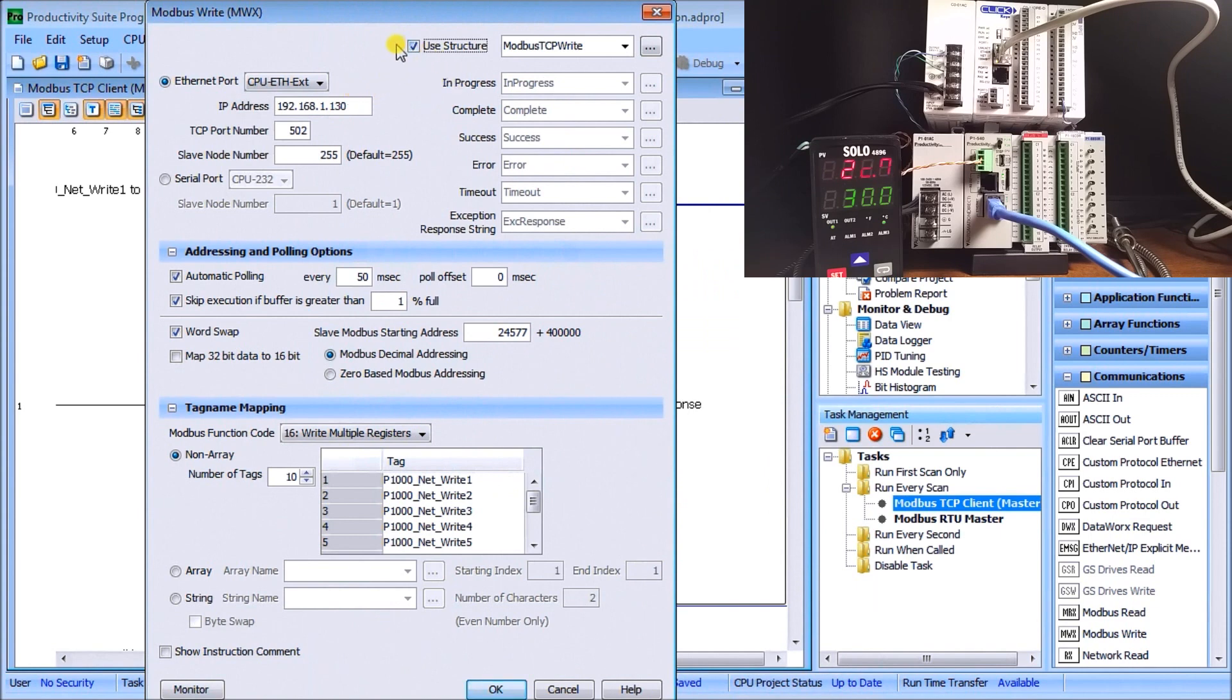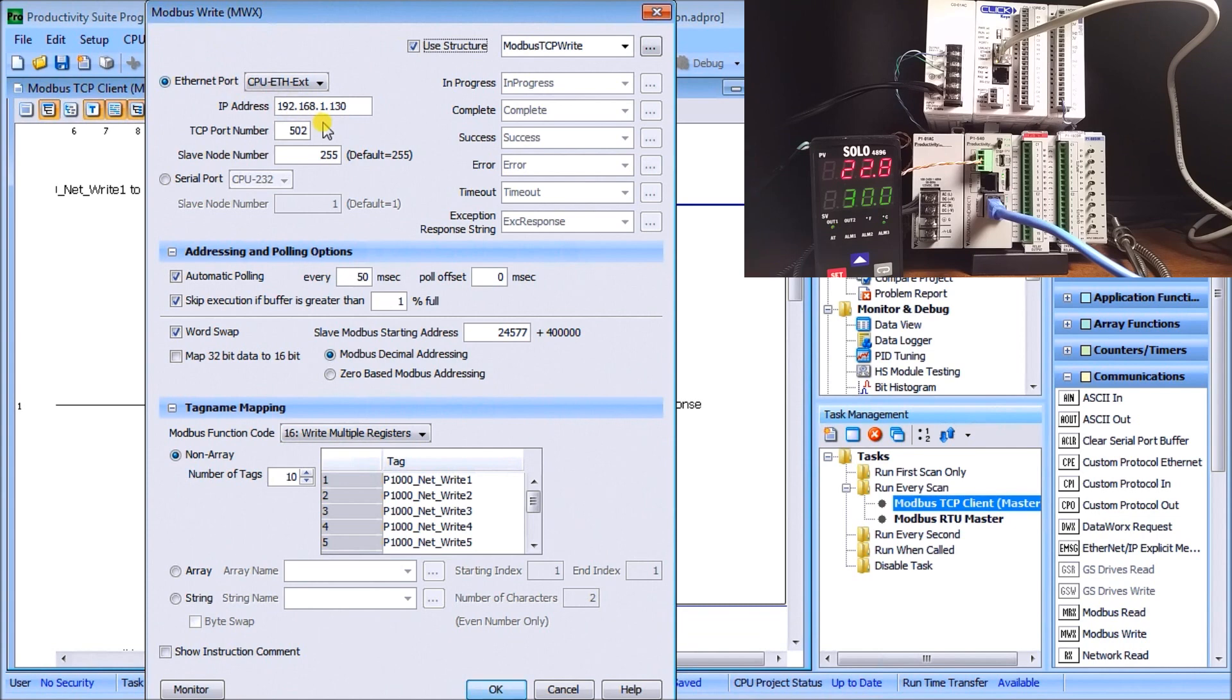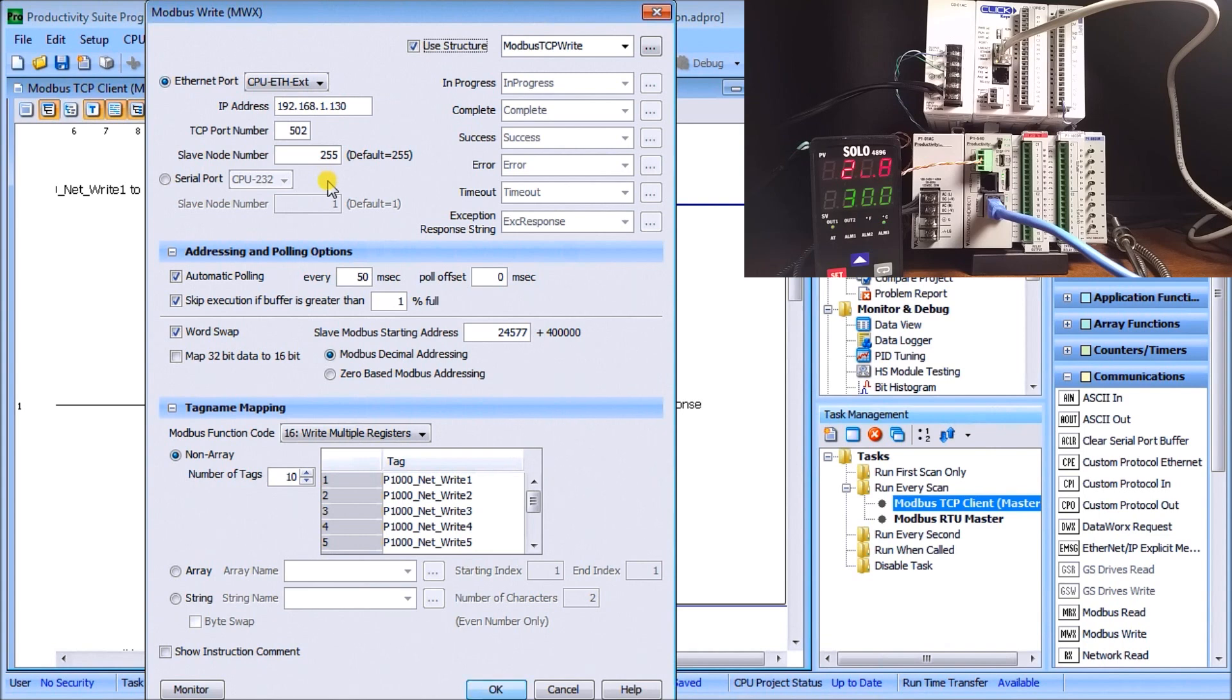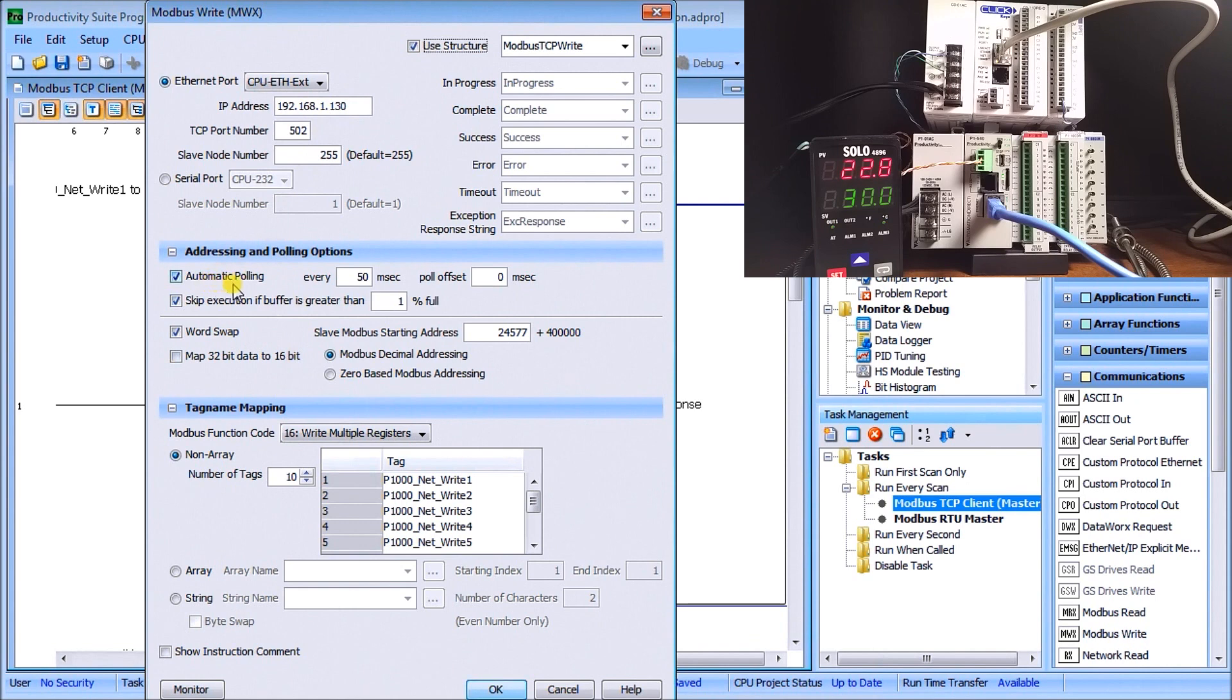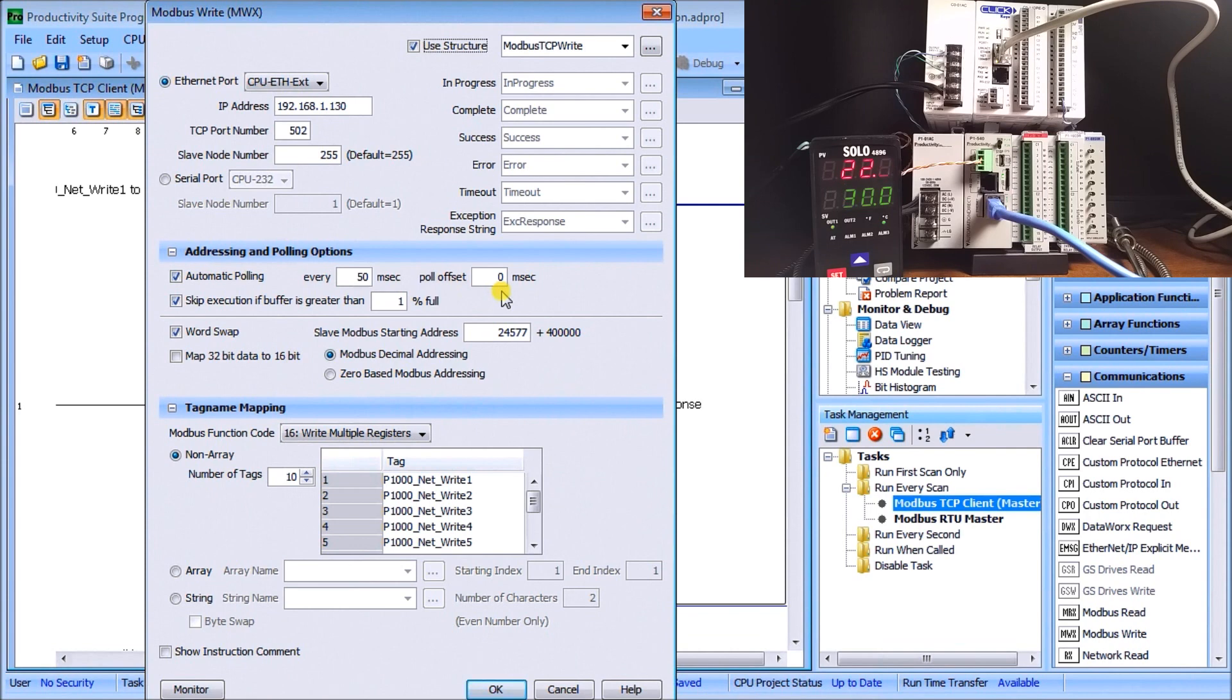What we're saying is we're using a structure and we're using our Ethernet port, and we're going to be talking to that address of the Click which is 192.168.1.130, the TCP port number which is 502, and the slave node number that we want to talk to. In this case, because we're talking Ethernet, it really doesn't matter because it's really going by the IP address. Then we go down here to the polling and we're saying automatic polling every 50 milliseconds with a poll offset of 0 milliseconds. What this means is as soon as it starts polling, it will automatically poll that device and then every 50 milliseconds after it keeps on going.